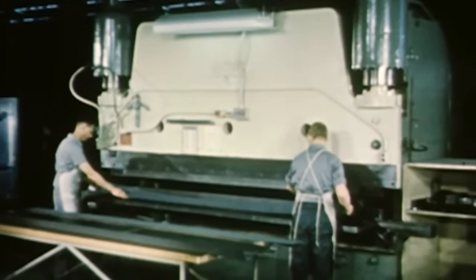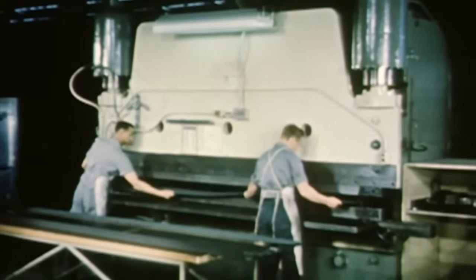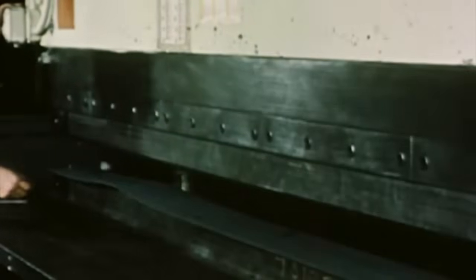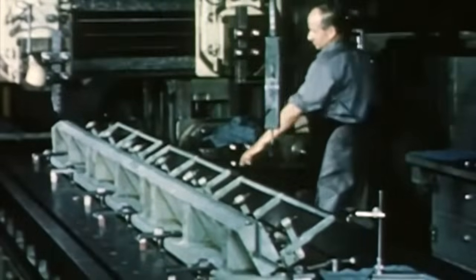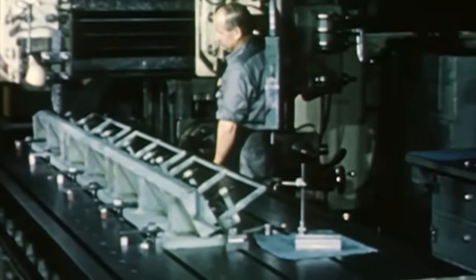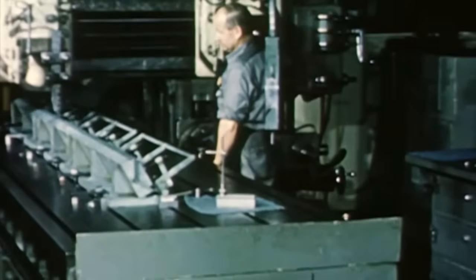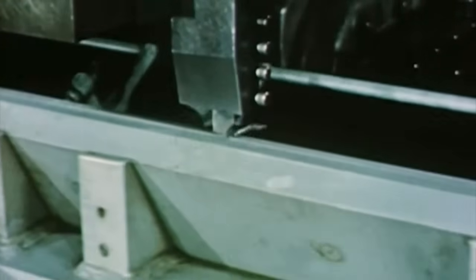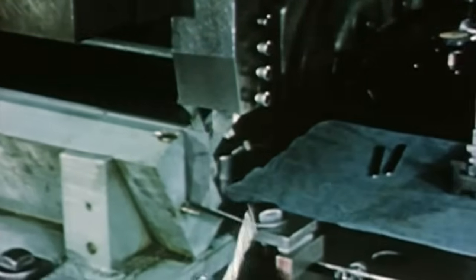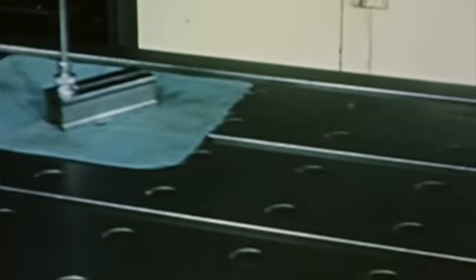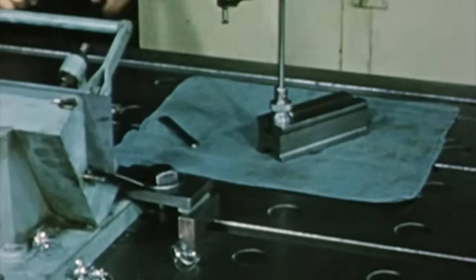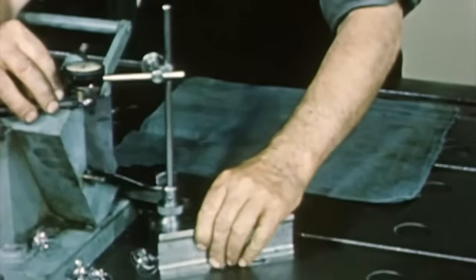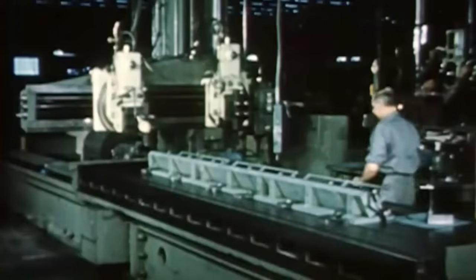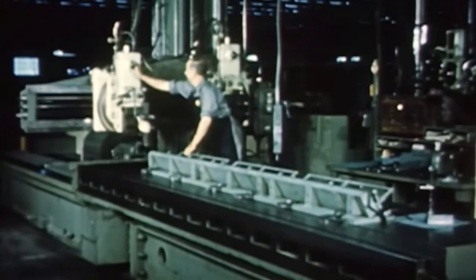The zirconium cans, which enclosed the graphite moderator blocks, were fabricated from 6 separate longitudinal panels. The formation of each panel was completed in a single break operation. This is a 60-degree bend. The formed panels were machined to the specified width. This operation was critical, since it determined the tolerance on the completed moderator can. After machining, the panels were cleaned by micro sandblasting, the final step before assembly.